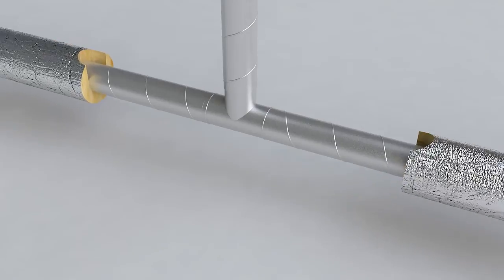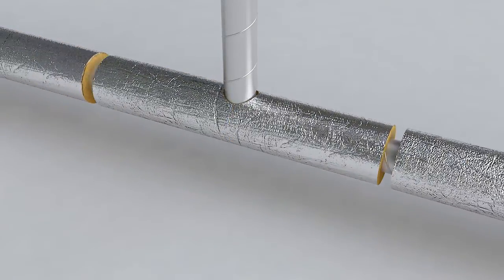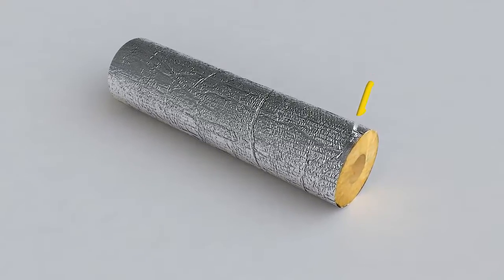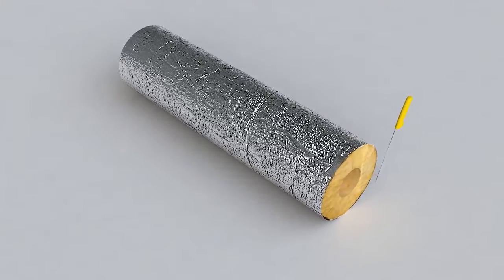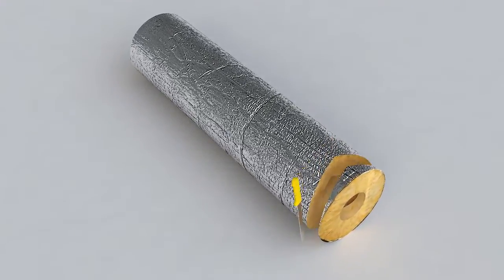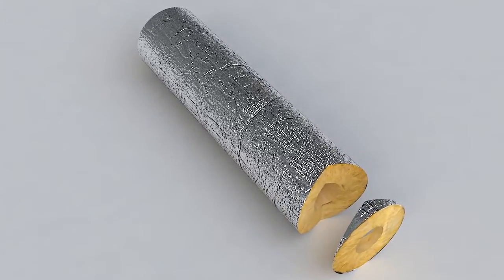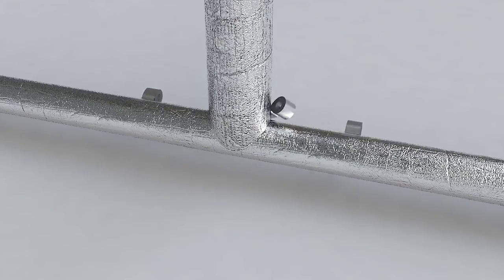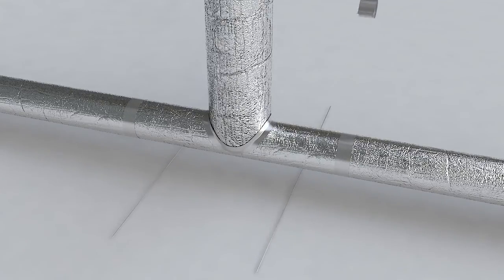The pieces are slipped into position and then the insulation of the main section is complete. For the projecting branch section, a piece measuring around 5cm is cut obliquely and removed. And then the insulation is slipped into position. The seams are taped and the insulation firmly secured with binding wire.